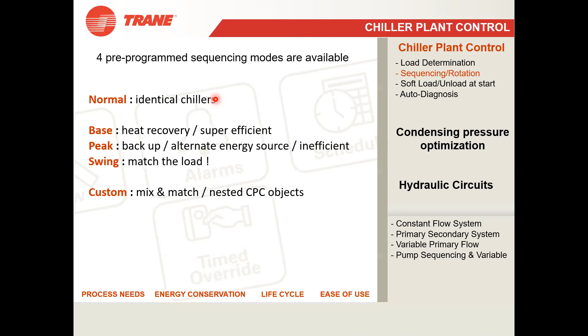Now, what is base mode? Suppose you have an old building that you are renovating, so some chillers are old and some are new. The old chillers will have lower efficiency, and the new ones will be super efficient. In base mode, you first start the super efficient chiller, and if needed at peak load, the less efficient or old chillers will start. That is called base mode.